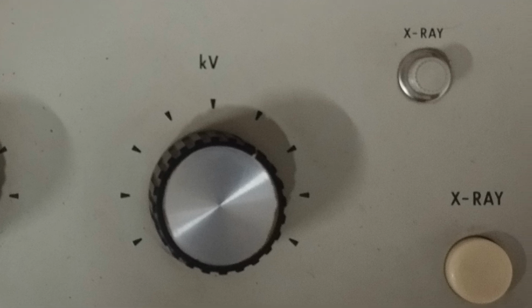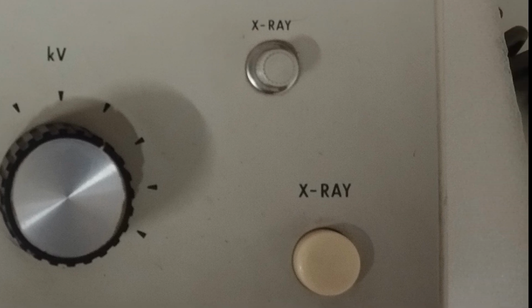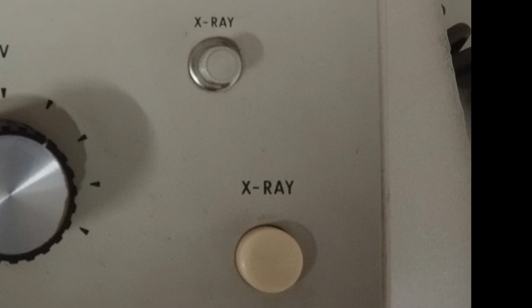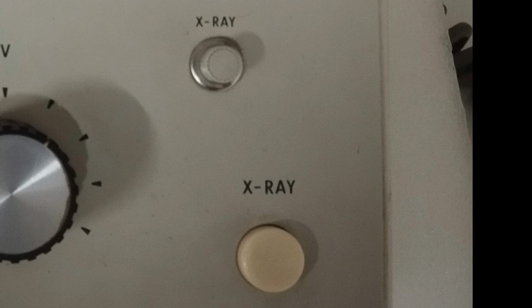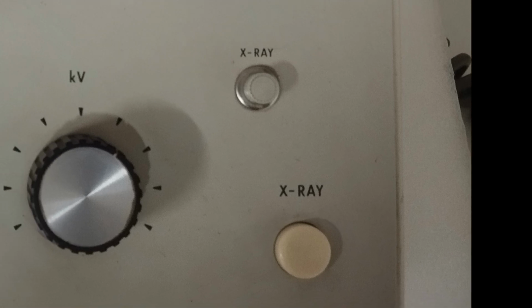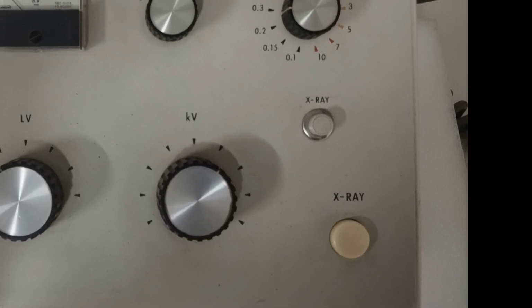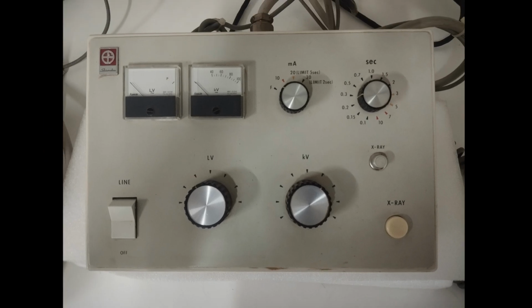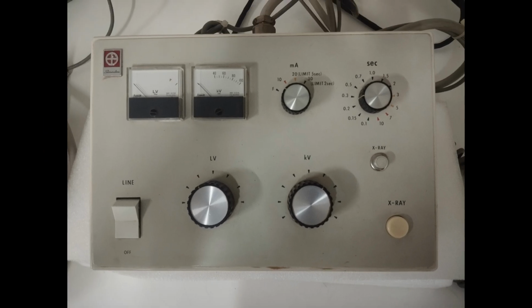To the right, you will find the X-ray activation button as well as the X-ray on warning light. This light will illuminate whenever X-rays are being generated. And lastly, on the top right is the timer control knob. By adjusting the time longer, one makes the image darker. As a result, you will find that the kV tends to change the contrast of the image, and the mA and the time combination tends to change the brightness of the final image.